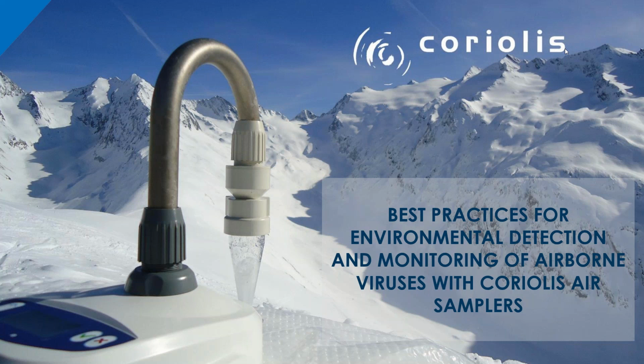The Coriolis Micro description, as you can see, the Coriolis is a small instrument, quite lightweight, at 2.8 kilograms. There is an autonomy of 1 hour of battery, but you can work with it up to 6 hours. The battery technology is NiMH. The airflow rate can be chosen between 100 to 300 liters per minute, and it collects, as we mentioned, any biological sample. It can be used indoor and outdoor, as it can be used on battery or on power supply.